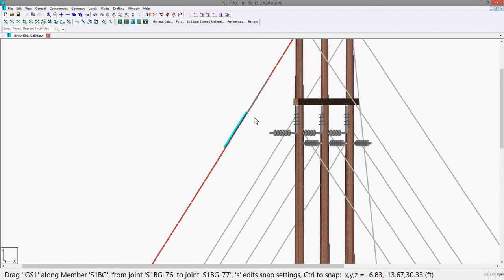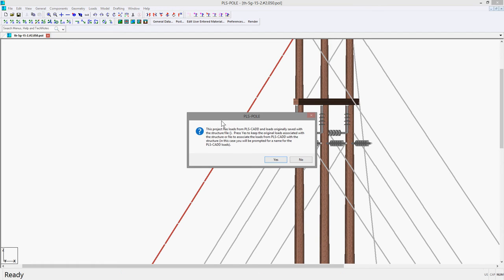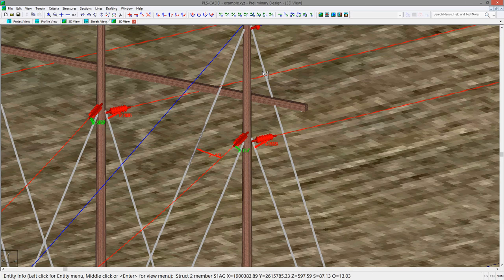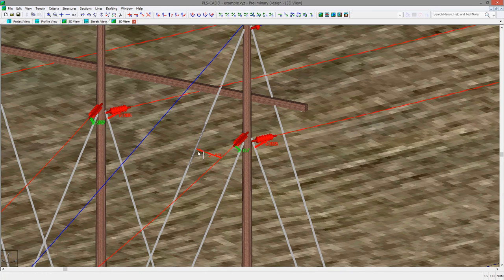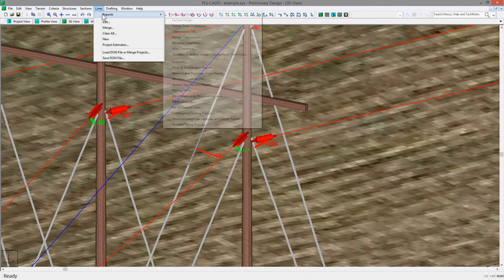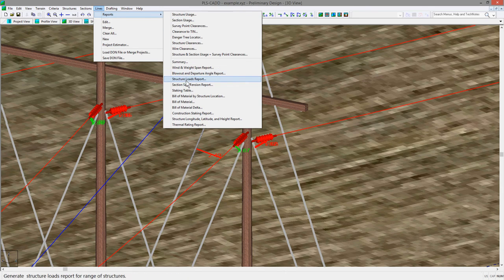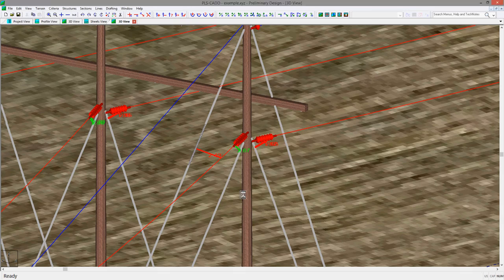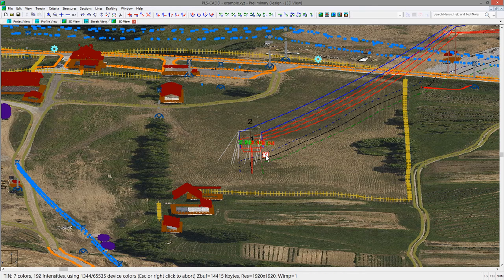After moving this, you can hit save and go back to PLSCAD. And you will see the model has been updated with the guy strain insulator. So now you can rerun the lines report structure clearances command. And if we look at the section with the new guy strain, it meets the clearance requirement with the clearance reduction factor of 0.75 that was input in the dialog.